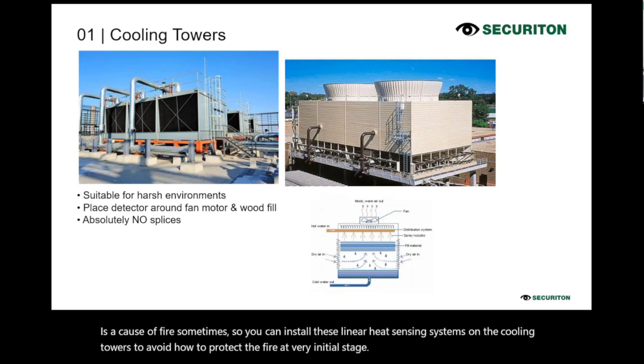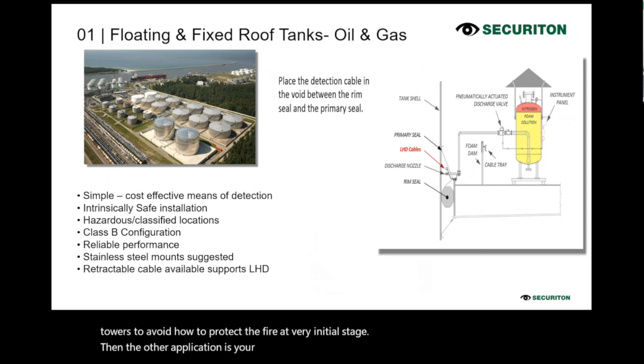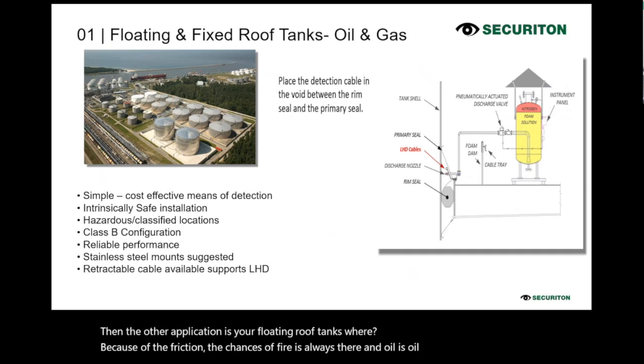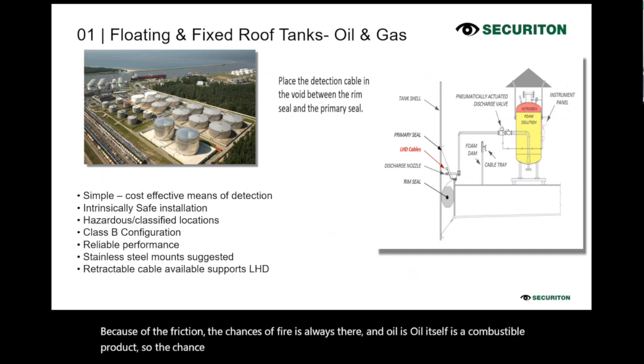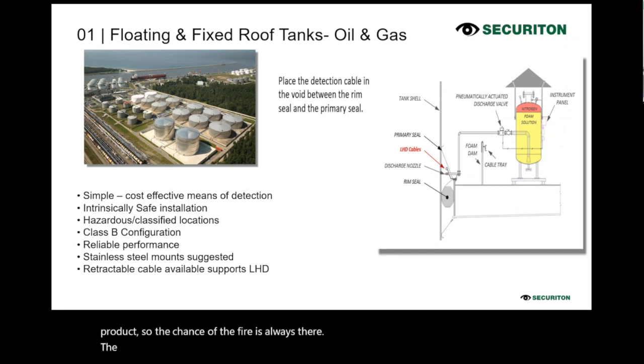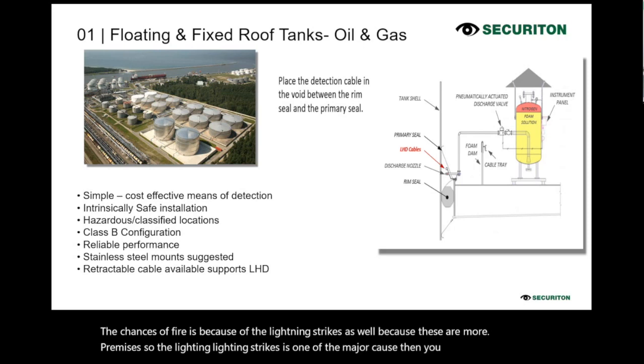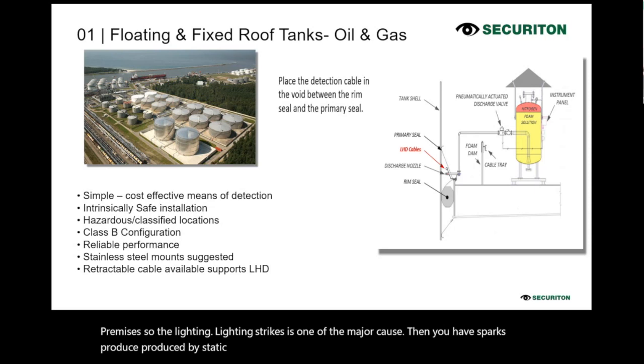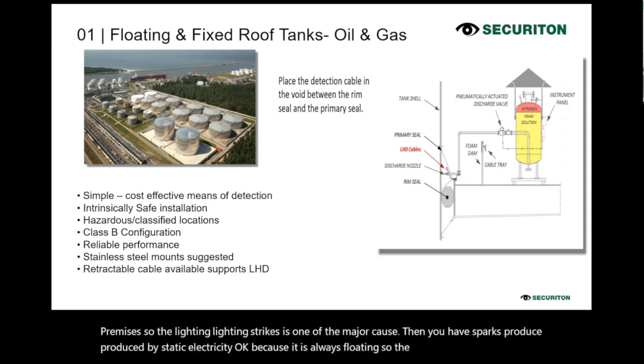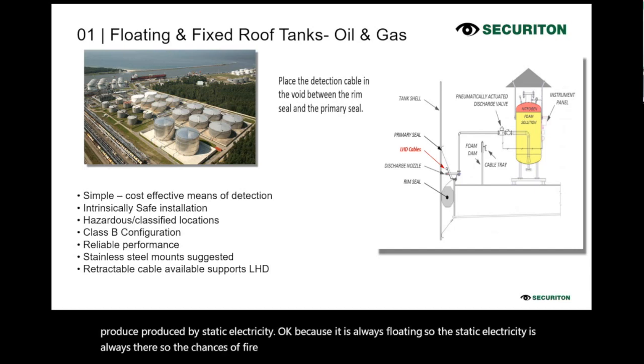Then the other application is your floating roof tanks, where because of friction the chances of fire are always there, and oil itself is a combustible product. The chances of fire are also because of lightning strikes, because these are open premises. So lightning strikes are one of the major causes. Then you have sparks produced by static electricity. Because the roof is always floating, static electricity is always there. If it is not detected and controlled in time, believe me, the fire will be immense. The fire will be huge.